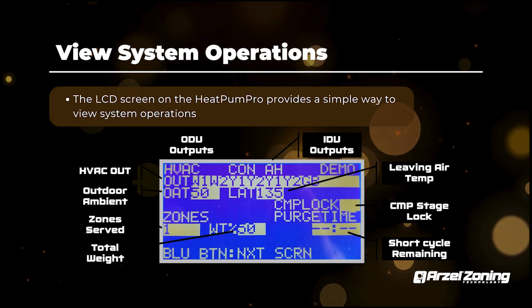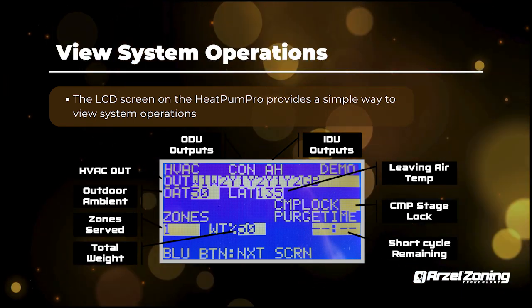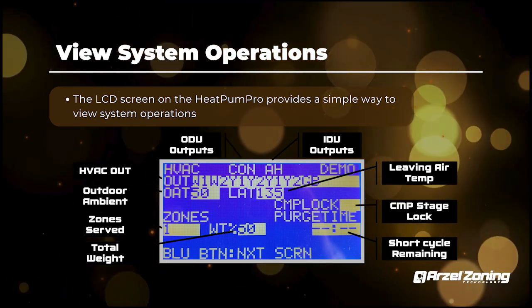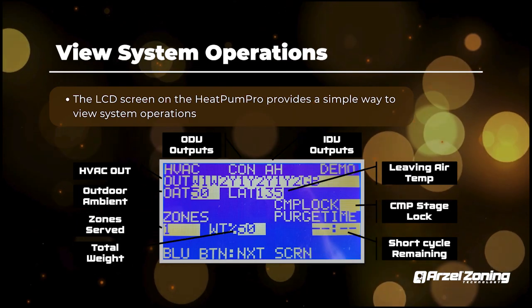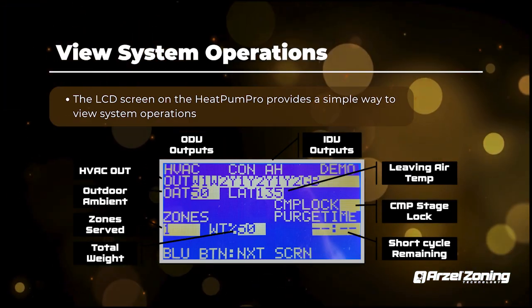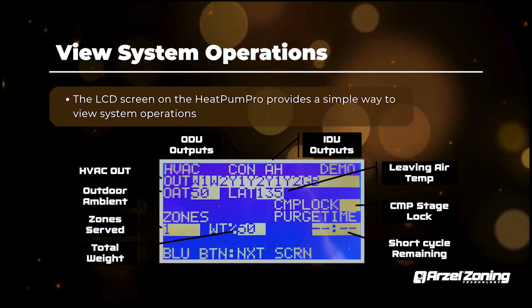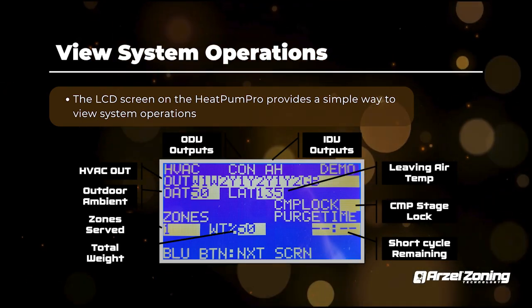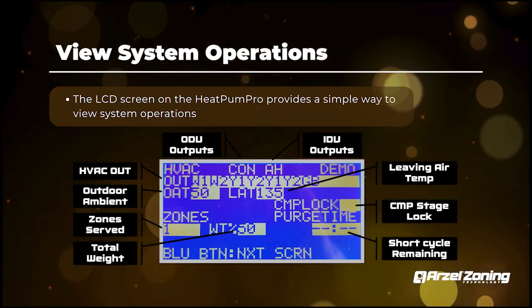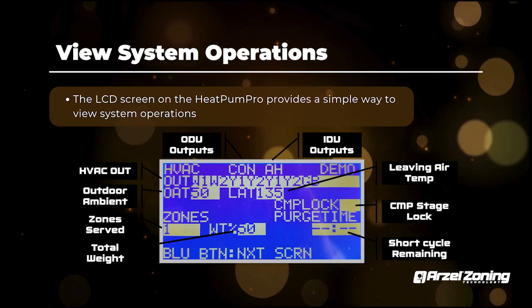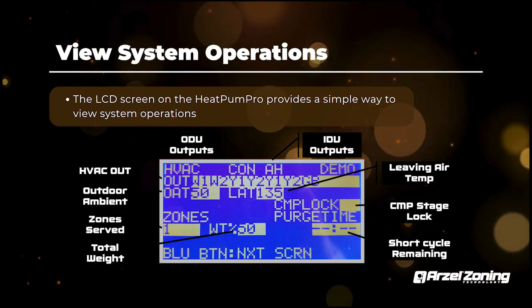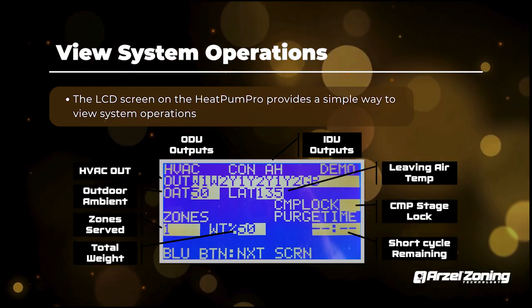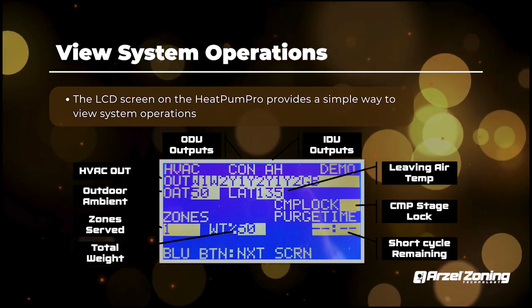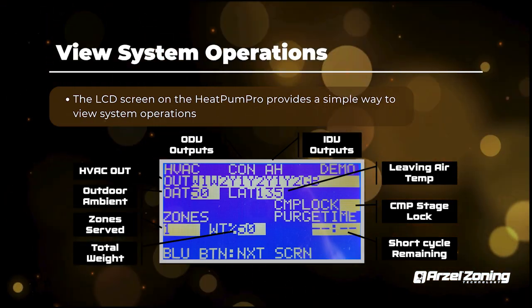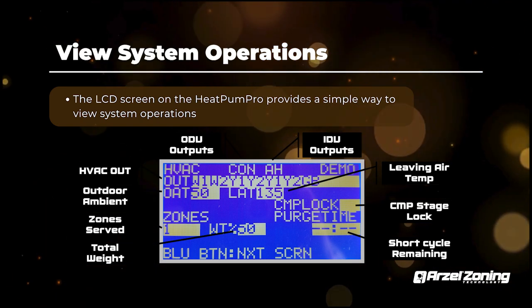Then kind of right underneath there, compressor lock and purge time. The only time you're going to see compressor lock is if we stage back your compressors. So if we got too hot or too cold in the ductwork, we drop out one of the stages of cooling or heating. You'll see that number. It'll either be a number 2 if we stage back from second stage, or it'll be a number 1 if we completely stage back. It'll be 1 and 2. It means it got way too cold in the ductwork. We shut your equipment off completely, and then you would just see a G on your output line, meaning we're trying to run just the fan to bring your temperature back up to re-engage your compressor.